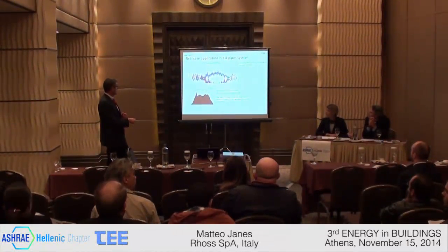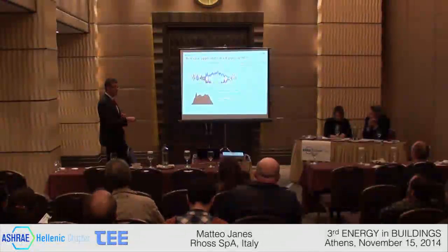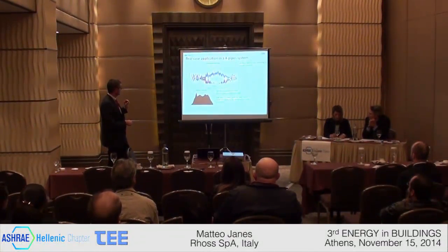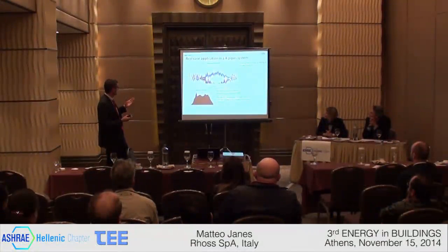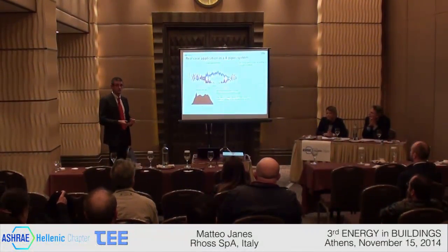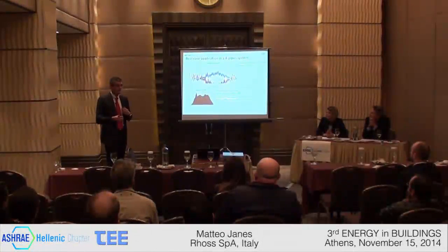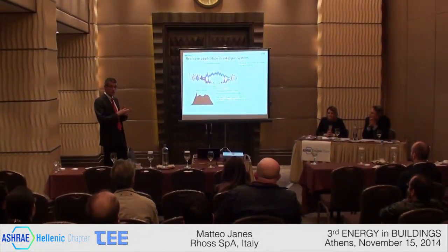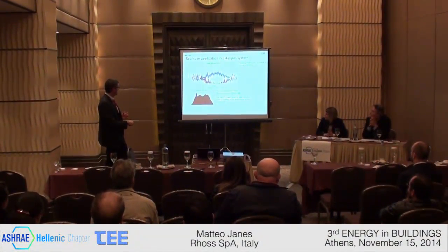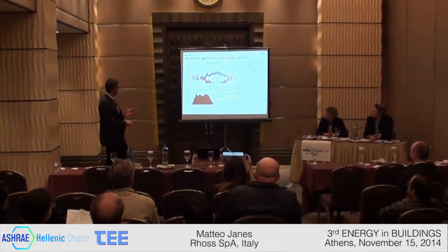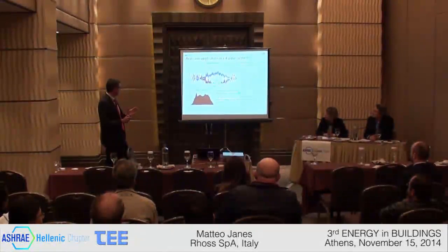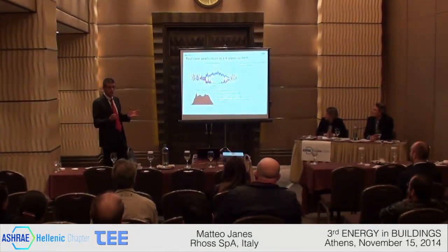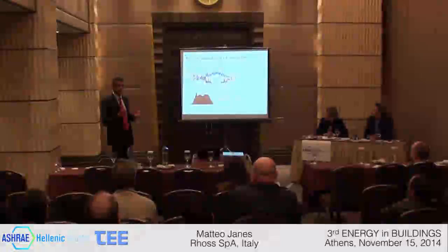This is the energy modeling of the building in Milan across the whole year. As you can see, a small amount of cooling is required all year round. The reason for this is that this is an office building with server rooms, with very high internal loads in terms of spotlights, crowded spaces, plasma screens, very strong insolation due to the large glazing of the window of the building. And this is the temperature profile in Milan. So how many hours per year we have at different temperatures. Temperature in Milan ranges from -5 to +35 Celsius all year round, which makes the use of a heat pump all year round economically convenient.